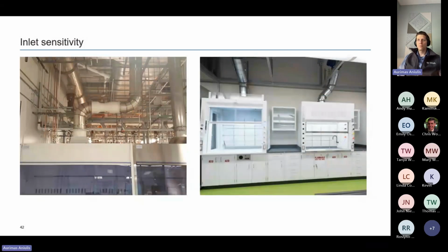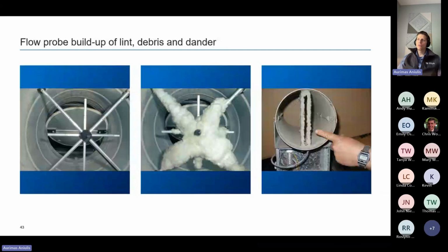Now, Venturis, that's the beauty of the technology. They don't care, right? As long as you're within the operating pressure range, whatever the swing inside of it is, that cone spring assembly will do what it's supposed to do. But the main reason you want to use a Venturi is this. This was a hospital in Boston, and this is how much lint accumulated in one year's time from a single patient room. It's because of all the linen changes. That is just general exhaust. It's not even fume hood exhaust, right?